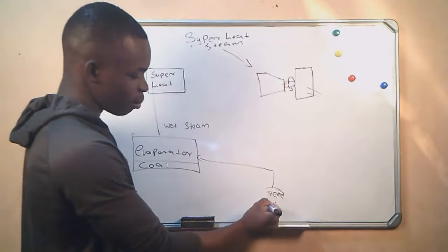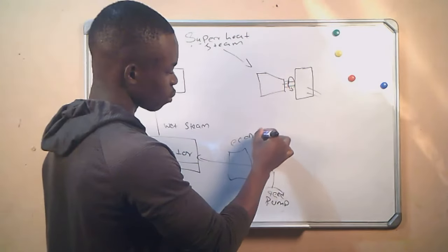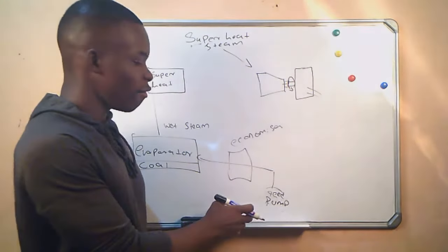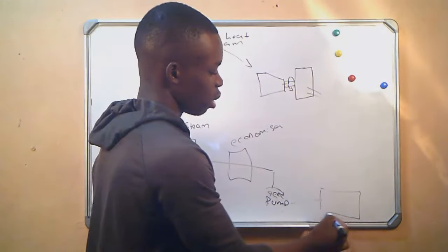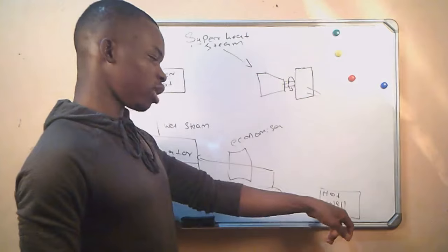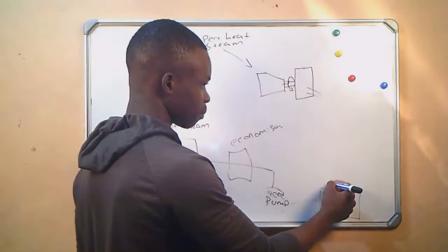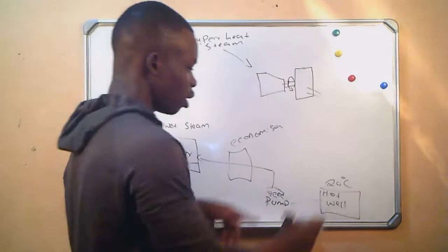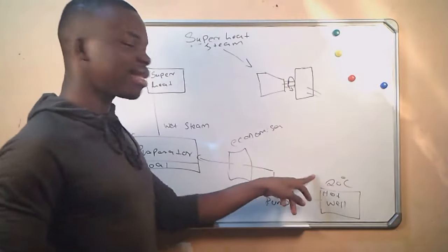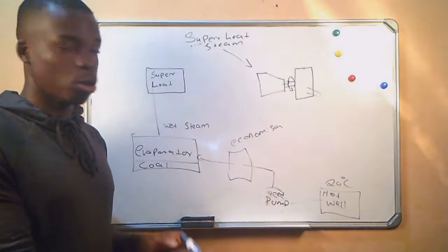Between the evaporator and the feed pump, we have an economizer. An economizer is used to raise the temperature of the water from what it is as it is coming from storage — we call the storage the hot well. The feed pump pumps the water from the dam. Let's say the water is at a temperature of 20 degrees Celsius. The water will be pumped from the hot well and then passed to the economizer, which will raise its temperature so that it becomes easier to evaporate the water when we reach the evaporator.